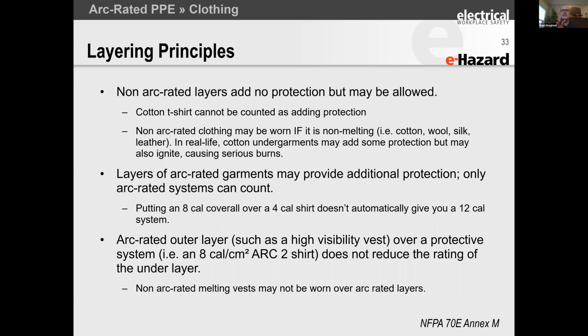Layers of arc-rated garments can provide additional protection, but only arc-rated systems count, because you can't take 8 calories and put it over 4 calories and know you have 12. You actually might still just have 8 because of the way the physics works.